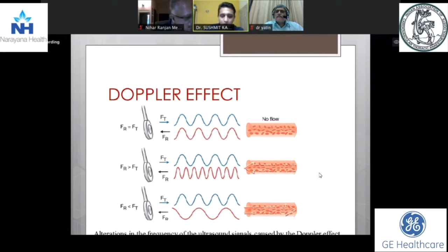Once we know the direction, to measure the velocity, we need to use a mathematical equation, that is the Doppler equation, in which the Doppler shift is directly proportional to the blood flow velocity and the cosine of the angle at which the Doppler beam makes with the blood flow. So if the beam is parallel to the blood flow, then cos of 0 will be 1, and we'll be able to accurately get the velocity. Whereas if the Doppler beam is perpendicular to the blood flow, then cos of 90 is 0, so we won't be able to appreciate any blood flow.